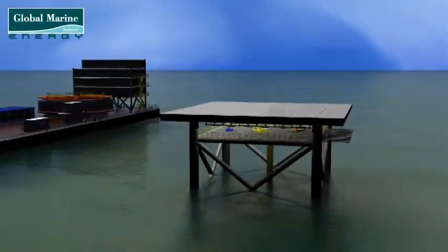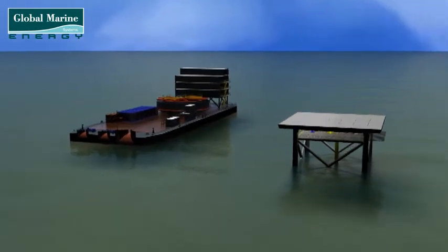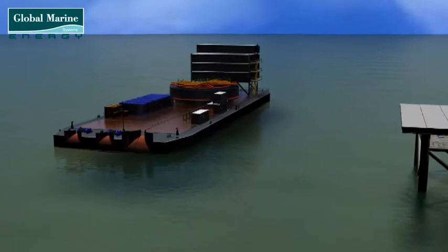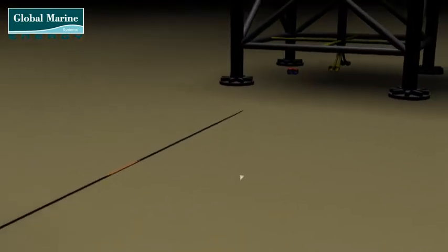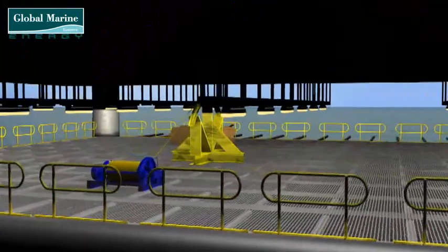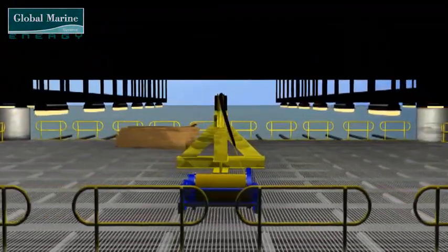A connection is made between the pulling line and the cable end. The cable end is then laid down on the seabed and the pulling line drawn back up the J-tube. Once the cable has been laid, the line used to lower the cable can be disconnected and the pulling phase can begin. Here, the excess slack is seen being drawn up through and out the top of the J-tube. This completes the operation, ready for the cable to be connected to the switchgear on the platform.